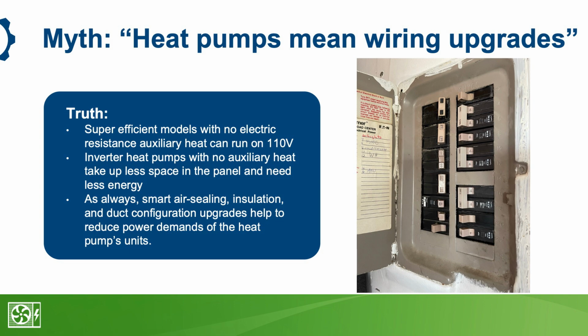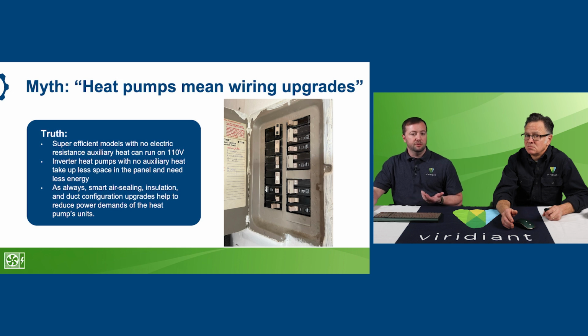Because that heat pump just needed a 30 amp and a 15 amp dual breaker, no additional breakers were needed. That was able to fit within the existing panel, and they were able to avoid an upgrade. Because it was a cold climate heat pump, there was no auxiliary strip heat needed, which would have required additional breaker spaces and may have necessitated a panel upgrade.